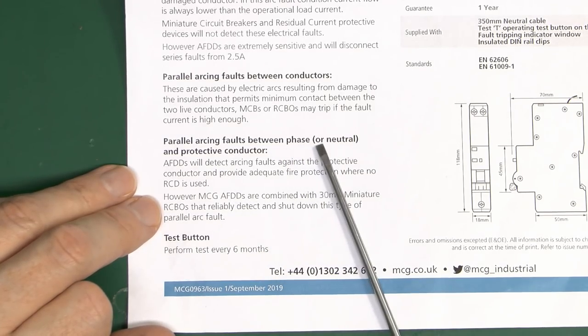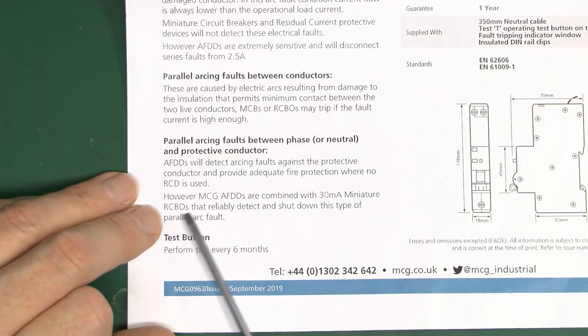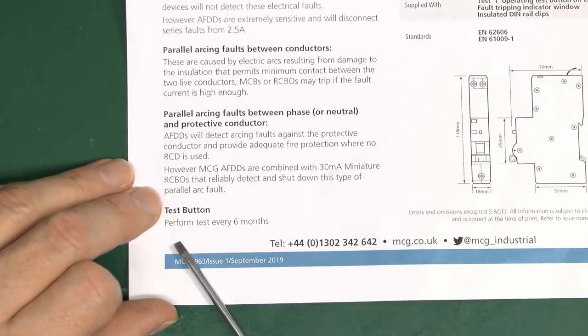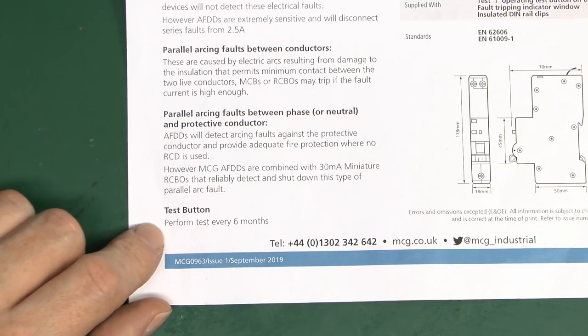For parallel arcs between phase or neutral and a protective conductor — yes, the AFDD can detect these, but ultimately it's the RCD that's going to detect that pretty much every time. That applies to any existing installation with an RCD.